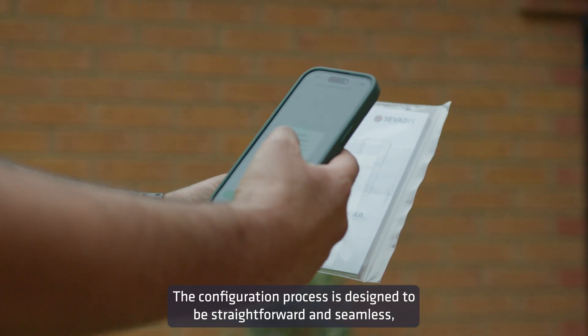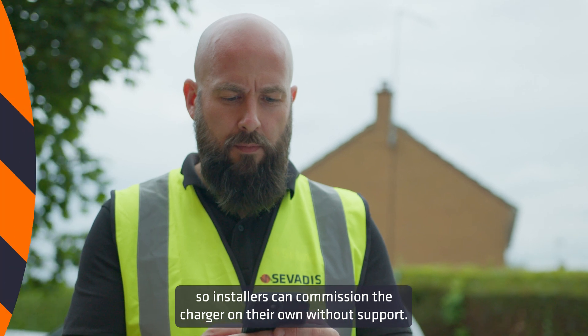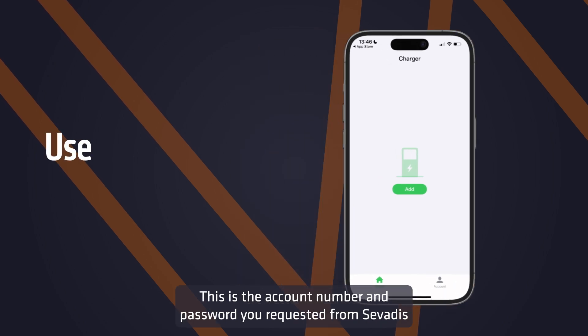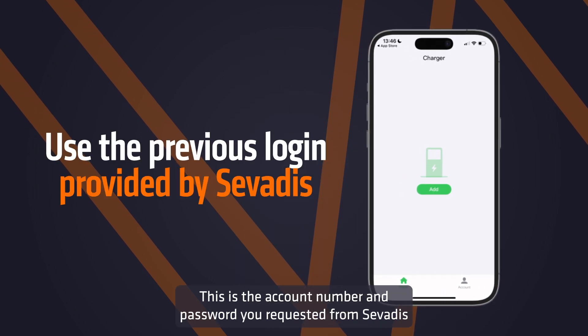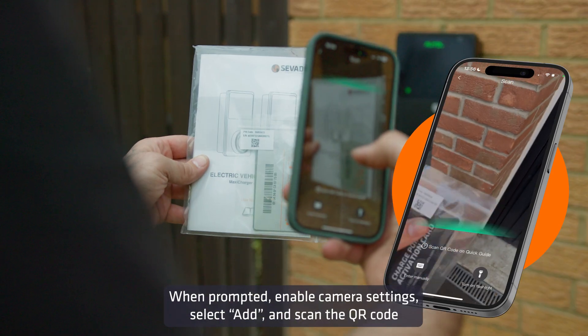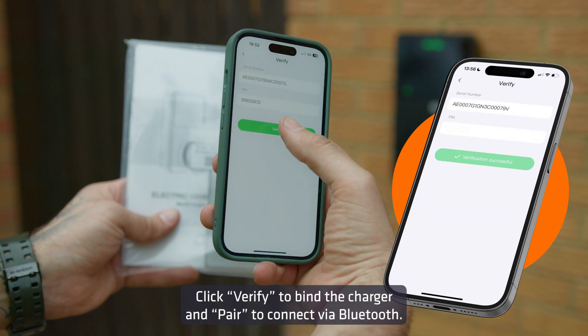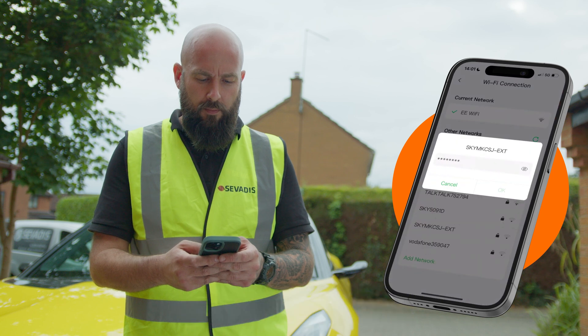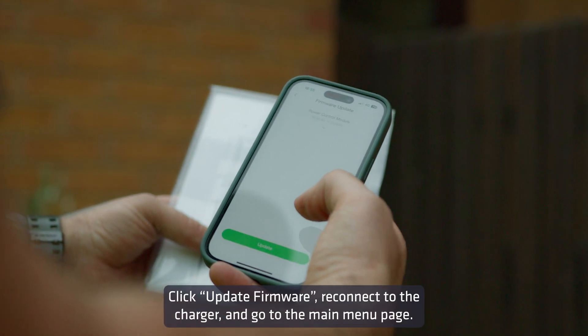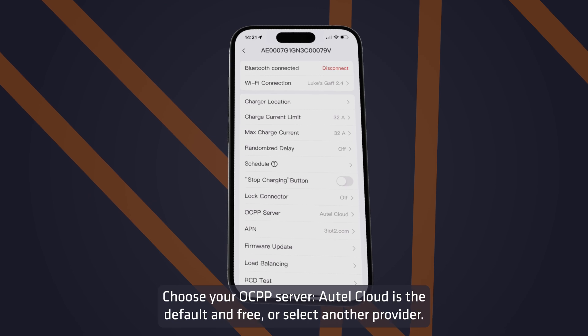The configuration process is designed to be straightforward and seamless, so installers can commission the charger on their own without support. Open the Autel Config app and log in using your assigned account number and password — this is the account you requested from Sevadis in advance of the install day. When prompted, enable camera settings, select Add and scan the QR code from the manual or RFID card pouch. Click Verify to bind the charger and pair to connect via Bluetooth. Set up Wi-Fi or Ethernet; for 4G, enter APN details. Click Update Firmware, then reconnect to the charger and go to the main menu page.